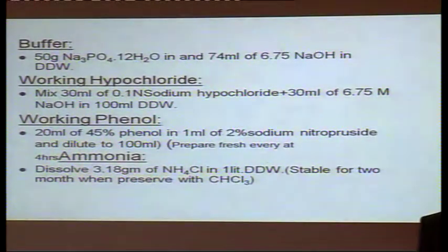When you are preparing this, those chemicals are to be exactly monitored. Other supporting chemicals need not be measured quantitatively; they do not play a quantitative role. They should be present in sufficient quantity throughout the analysis. And whenever you change the chemical process or you repair the instrument, you should again prepare a calibration graph, a standard graph, or ideally always run the standard with the samples. There is a cross check.